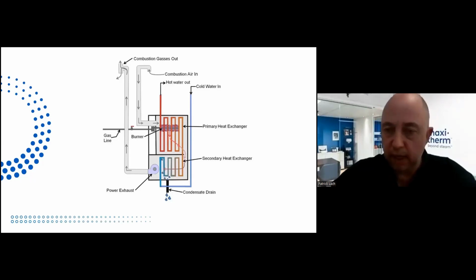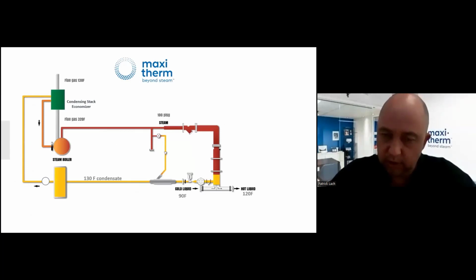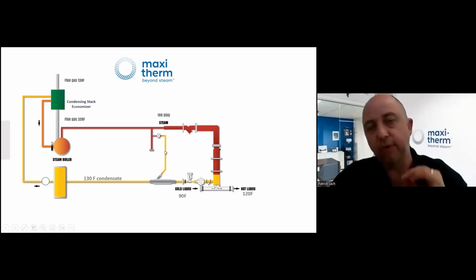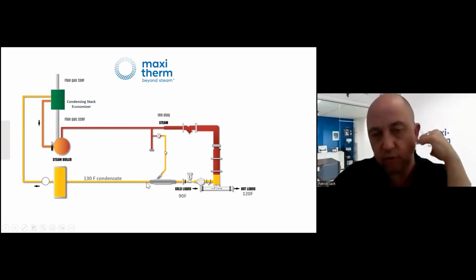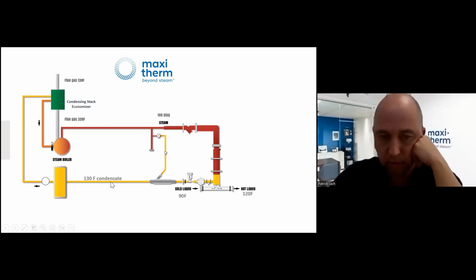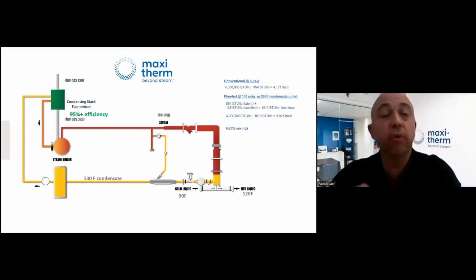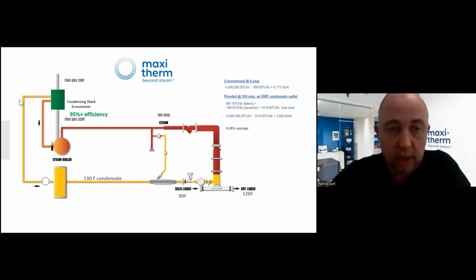So let's apply this to Maxi-Therm. Let's control a 120 Fahrenheit outlet temperature on the hot water side with a potential return at 90 Fahrenheit at full load. We can oversize the heat exchanger, so that at full load, instead of coming out at 200 Fahrenheit, we will come out at 130 Fahrenheit. If you had a condensing stack economizer on the chimney, well, that's what I'm going to show you in a few slides, how we can reach this, okay?